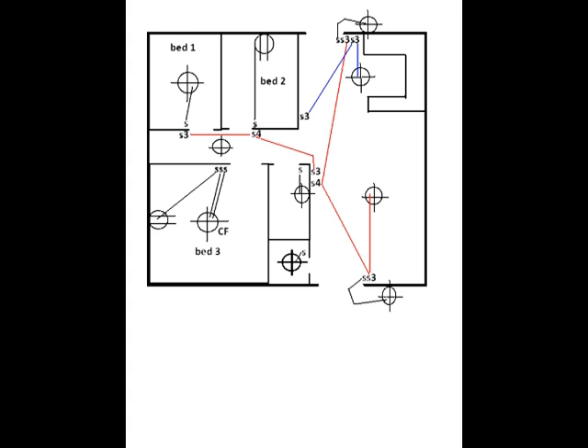Let's move to the living room. You have to have a switch at the entryway, another switch which is a four-way switch at the hallway, and then back to a three-way switch at the back entrance of the kitchen. There's a total of three switches that operate the living room light.